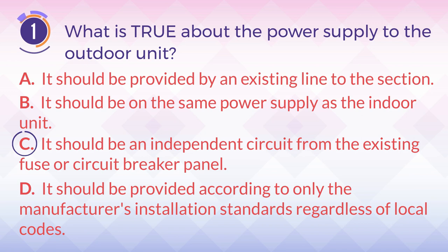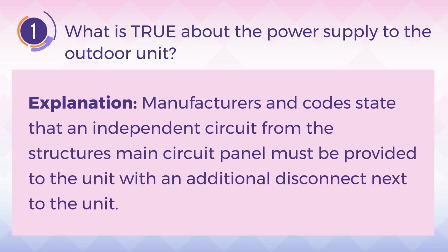regardless of local codes. The answer is C. It should be an independent circuit from the existing fuse or circuit breaker panel. Explanation: Manufacturers and codes state that an independent circuit from the structure's main circuit panel must be provided to the unit, with an additional disconnect next to the unit.